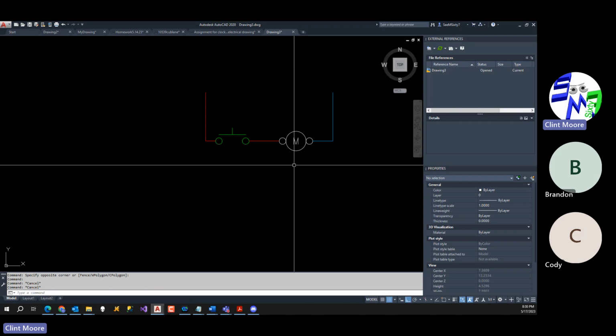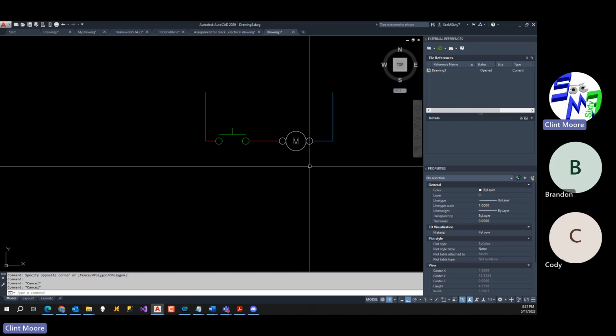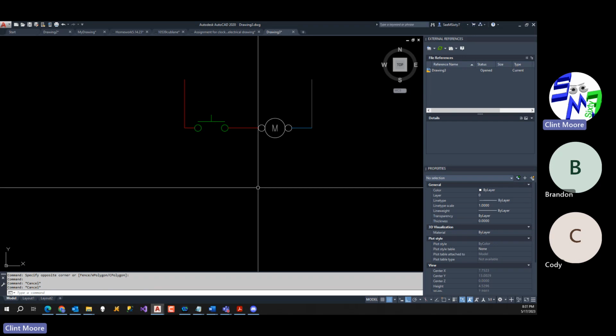So if you have a coil in your hand or a relay in your hand, and it says there are two normally open connections and two normally closed connections, that means that without doing anything to it, those two normally opens are open. They're not connected. The two normally closed connections are closed. So if you were to put a continuity tester across each side of the closed connections, you would get a beep or a buzz, showing there's continuity. And if you do the same thing to the normally opens, they would not be connected. But the second the thing is energized, all that would flip. The normally closed connections become open, and the normally open connections become closed. That's a little bit confusing sometimes to a lot of people, but we'll get into that a little bit more here in a bit.